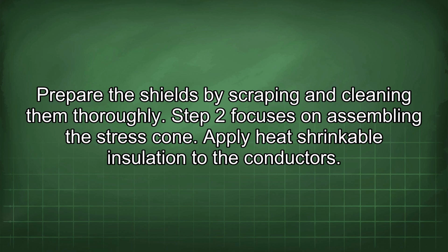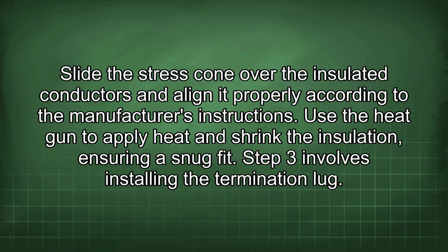Step 2 focuses on assembling the stress cone. Apply heat-shrinkable insulation to the conductors. Slide the stress cone over the insulated conductors and align it properly according to the manufacturer's instructions. Use the heat gun to apply heat and shrink the insulation, ensuring a snug fit.